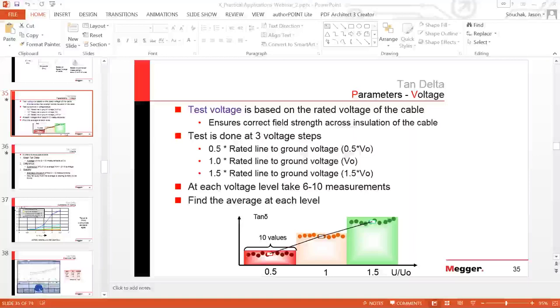And you might also have a combination of temperature, but also mechanical, because as you are well aware, if you have a lot of changing temperature from loading, from changes in loads, you also get thermal expansion and contraction. So you have also now the mechanical aspect of aging. And sometimes some cables are not always all the way buried. There might run a cable trace above ground somewhere. You have UV radiation from the sun, and those cables see the UV during the day, and they have much more temperature change from day to night than a direct buried cable.